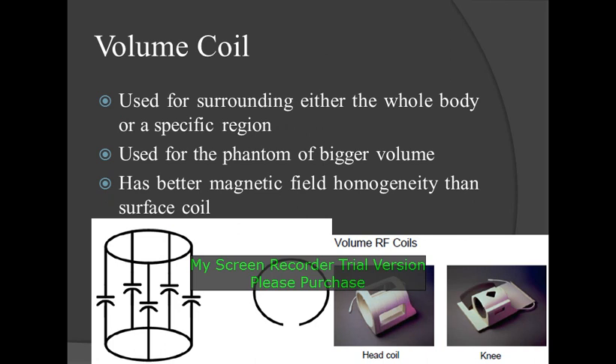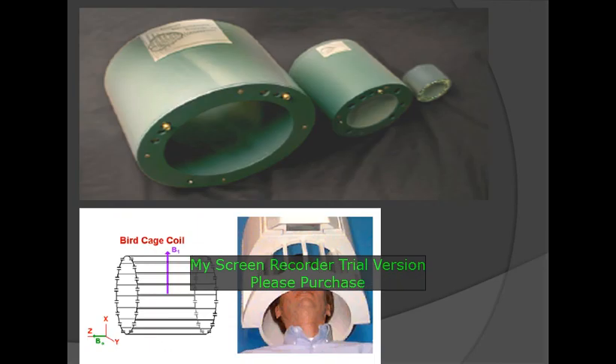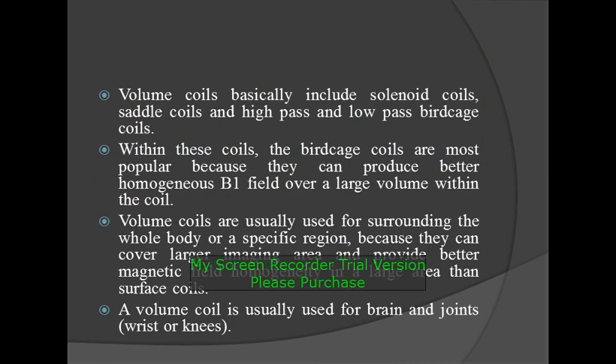Volume coils are used for surrounding either the whole body or a specific region. They are used for phantoms of bigger volume and have better magnetic field homogeneity than surface coils. Volume coils basically include solenoid coils, saddle coils, and high-pass and low-pass birdcage coils. Among these, birdcage coils are the most popular because they can produce a better homogeneous B1 field over a large volume. Volume coils are usually used for surrounding the whole body or a specific region, covering a larger imaging area and providing better magnetic field homogeneity than surface coils. A volume coil is typically used for brain, joints, and also wrist or knee joints.